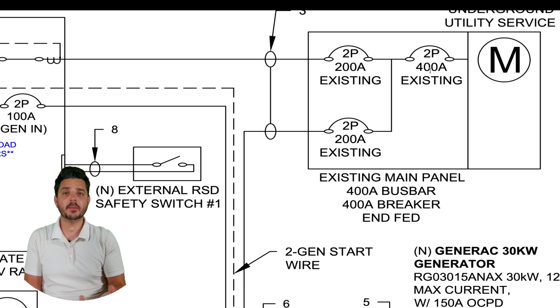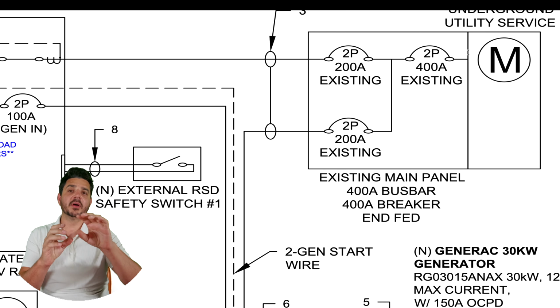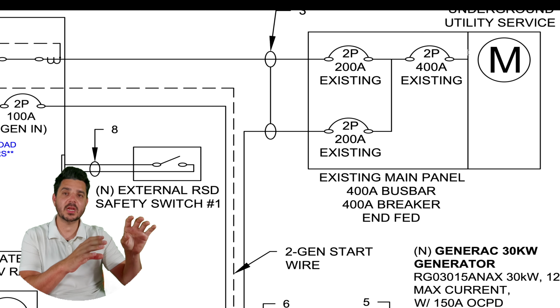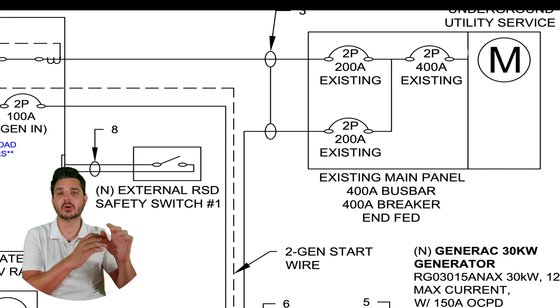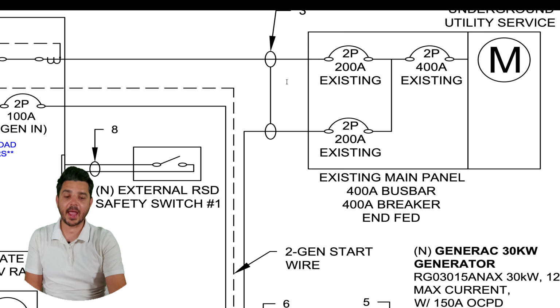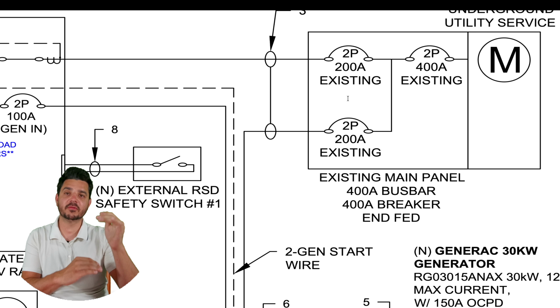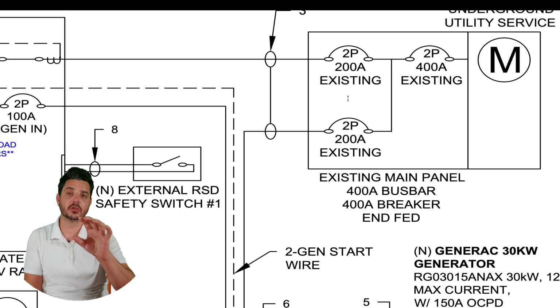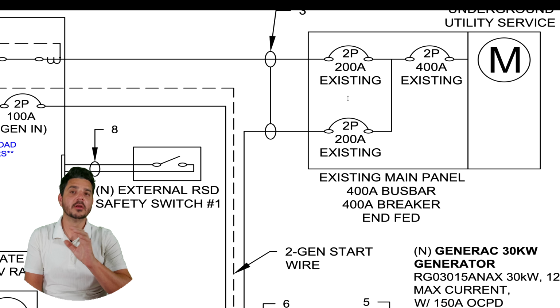Typically what happens is you have a 400 amp residential panel and it comes into the meter as 400 amps, but the second it goes past the meter, it's split into 200 amps. Similar to how this diagram is shown, but this panel actually has a 400 amp bus bar with 200 amp breakers on it. Totally different.